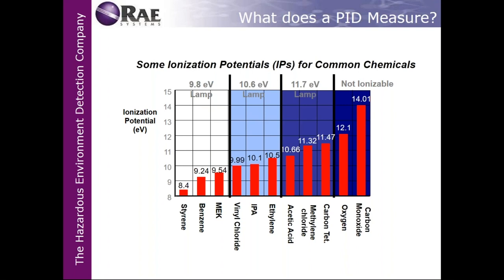It just talks about the basics of what the difference is or why you would use different types of lamps. If you're looking at something that has a very low eV, like styrene, benzene, or MEK, I wouldn't go with a 10.6. I'd go with a 9.8 lamp. Why? Because it's under 9.8. You'll get interferences. If you have a mixture, especially, and you're looking for benzene or styrene, if you have a 10.6 lamp, it's just going to pass on by. So you really just don't want to be interfered by the higher eV, so go with a 9.8 lamp.